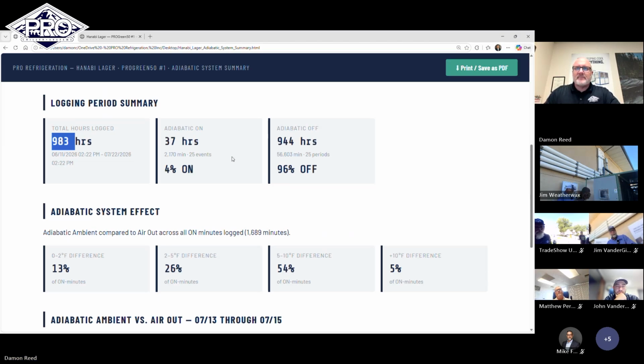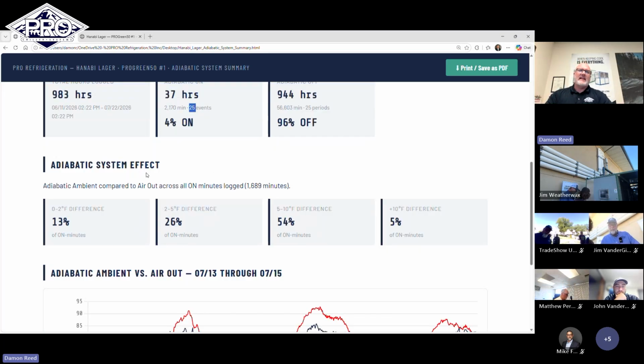Okay. 25 different occasions, broken down into different time slots. We looked at the adiabatic system effect. So over the time when we were on, what was the temperature coming into the pads versus coming out? And these are the different degrees of temperature difference. 13% of the time we were 0 to 2 degrees of temperature difference. Almost 30% of the time we were 2 to 5 degrees. We were 5 to 10 degrees 54% of the time. And we were more than 10 degrees 5% of the time.